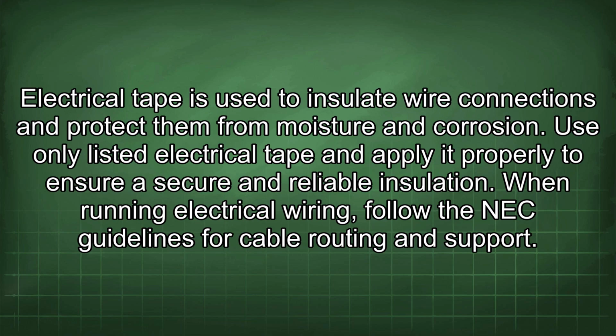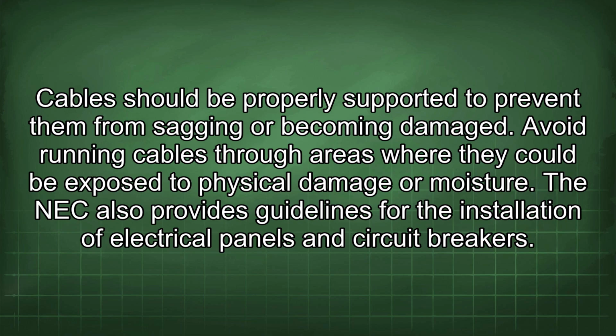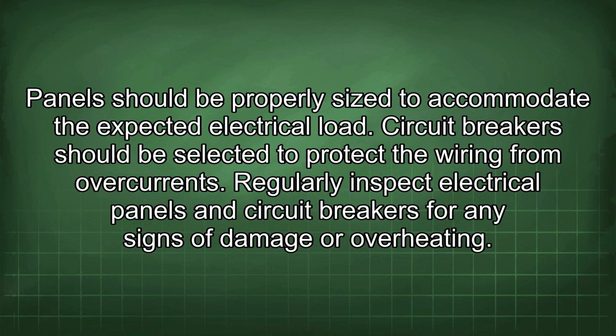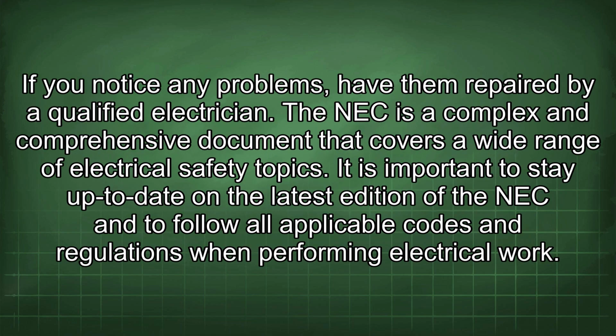When running electrical wiring, follow the NEC guidelines for cable routing and support. Cables should be properly supported to prevent them from sagging or becoming damaged. Avoid running cables through areas where they could be exposed to physical damage or moisture. The NEC also provides guidelines for the installation of electrical panels and circuit breakers. Panels should be properly sized to accommodate the expected electrical load. Circuit breakers should be selected to protect the wiring from overcurrents. Regularly inspect electrical panels and circuit breakers for any signs of damage or overheating. If you notice any problems, have them repaired by a qualified electrician. The NEC is a complex and comprehensive document that covers a wide range of electrical safety topics.